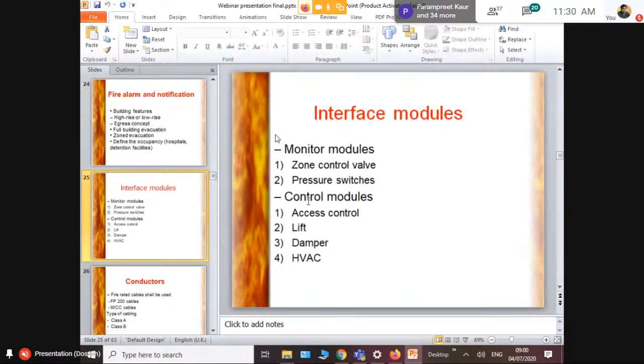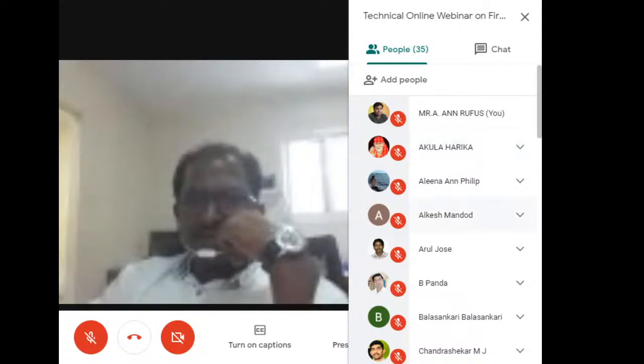What is a monitor module? We will have zone control valves, pressure switches, and systems which are being monitored by the fire alarm system. These systems will be connected to the fire alarm through a monitor module. How a pressure switch works and so on, we will see in the second session when my colleague comes in. So these systems will be monitored by the monitor modules and control modules. So you identify fire in a facility when you identify a rise in temperature.